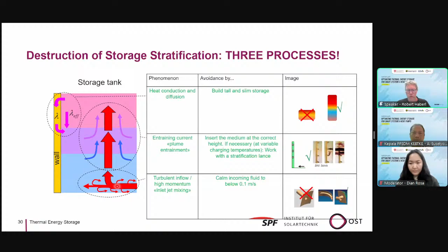So first, tall and slim storage tanks to avoid the heat conduction. Use stratification lance or the correct position of inlet to avoid the plume entrainment. And the third is calming down the fluid to a velocity below 0.1 meter per second. There are different measures to do that, and I will show you some bad and good examples for that, slowing down the speed of the fluid.